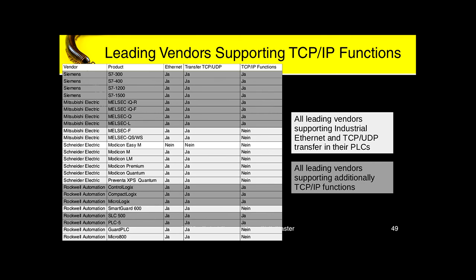Whether it's in fact possible, we don't know. But what we do know is that the S7-300 and 400 should be really easy, because those protocols are well understood. And the access protection is available, but of course it's turned off. What we also know is that on the 1500 and version 4, it does not work. The protocols have changed, and they just look different. And the big problem is that I do have a 1200, and I can't just use version 4. That just doesn't work. It's hardware version 3, so I can't install that. So I have to buy new PLCs, which is maybe part of their business model, I don't know. But it may not be possible to do a firmware upgrade if you don't buy the newer hardware.